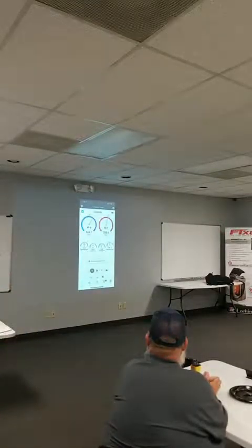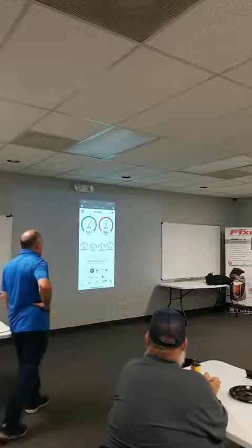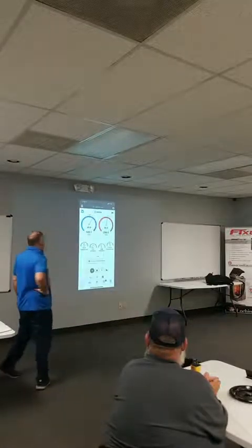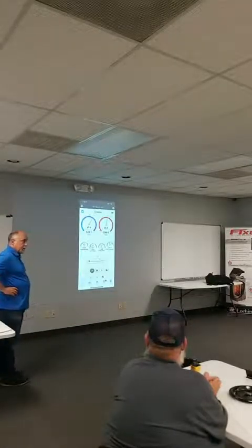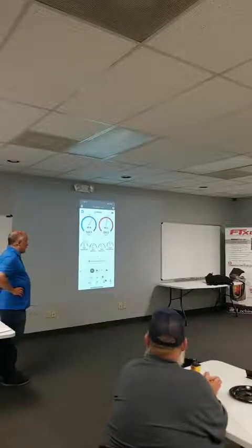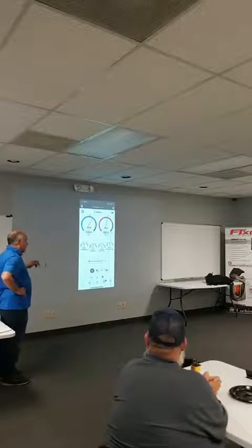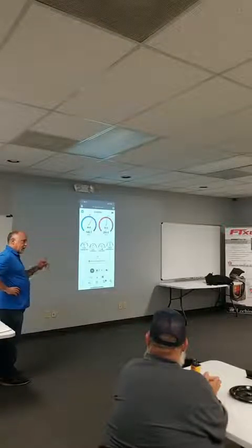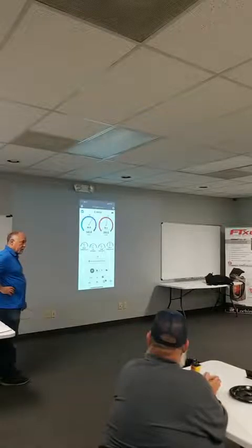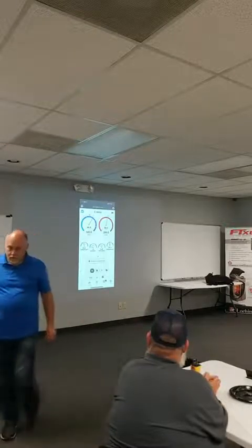Yet our head pressure on the machine's just fine. Why is our head pressure fine in the machine? There's not a lot of load. There's still enough condensing space in there, right? So you can't just look at pressures and temperatures on their own without looking at the other variables on the machine, right? Basically a big dehumidifier back there right now.